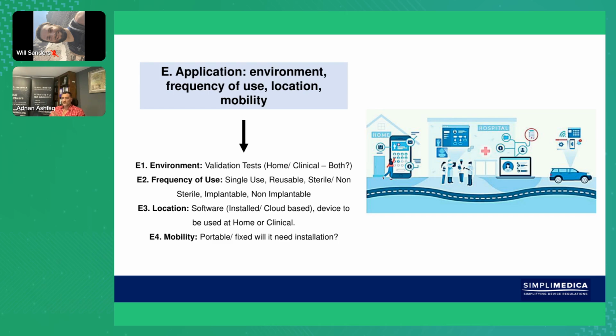So sterile, non-sterile, right? If it's sterile, again, we've got to use all the correct symbols on it. But we would have mentioned that in the intended use, that this device is indeed a sterile device or a non-sterile device. Is it implantable or non-implantable? If it's software, is it going to be installed? Is it cloud-based? Is it to be used at home or clinical? If the device is portable or if it's fixed. If it's fixed, it needs installation.